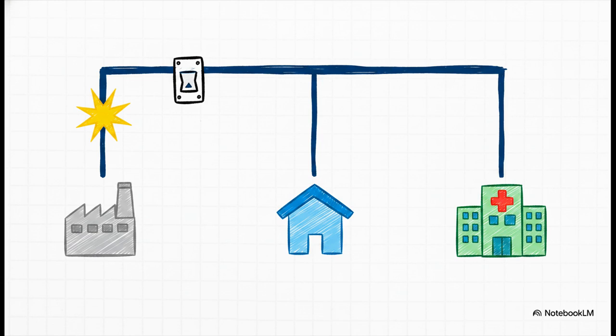This intelligent, tiered response is called selective clearing. The goal is to make sure that only the smallest possible piece of the grid gets disconnected to isolate a fault. It's what stops a problem on a single street from causing a citywide blackout. It's what keeps the lights on for everyone else.